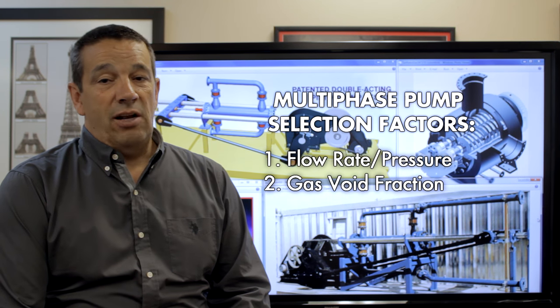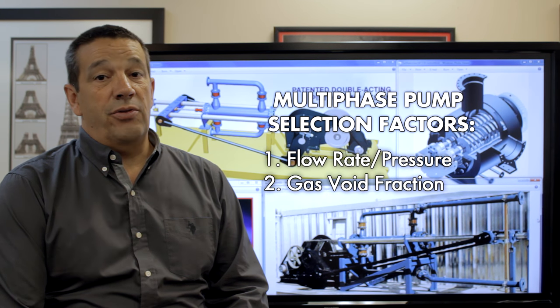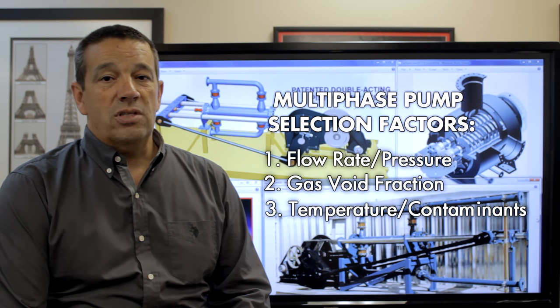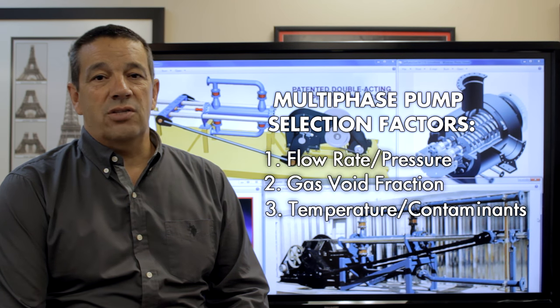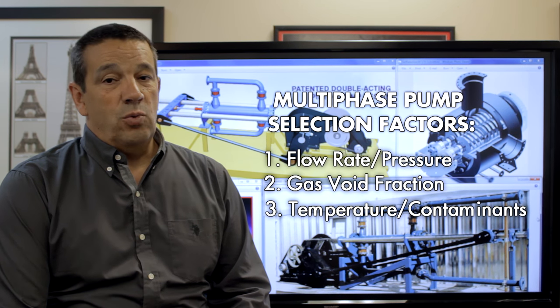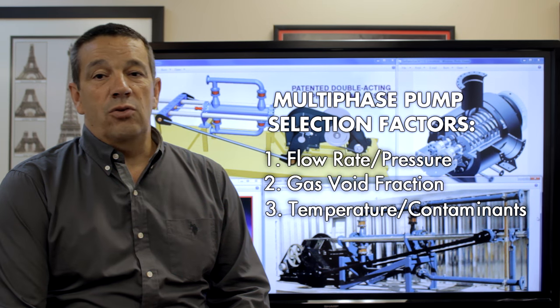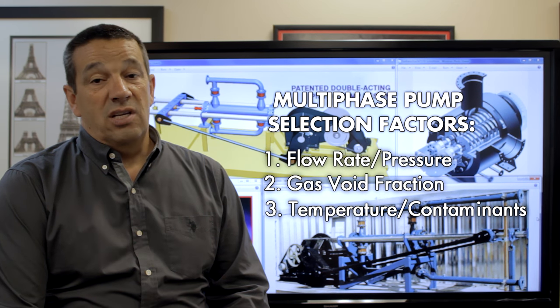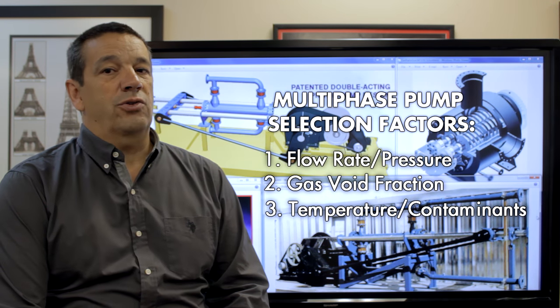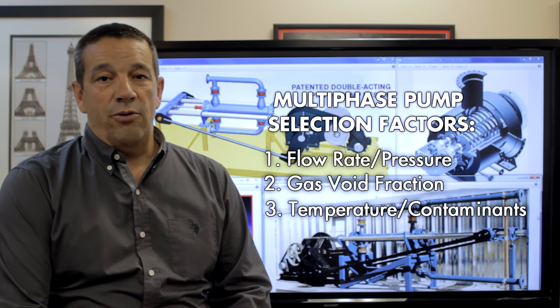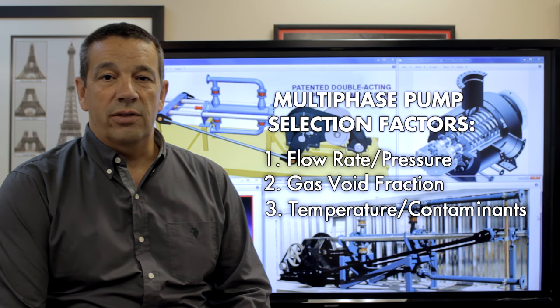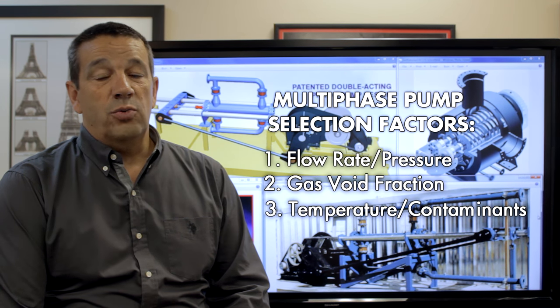Some pumps handle gas void fraction better than others. The other things to consider are temperature and contaminants. Temperature is important — when we're looking at SAGD projects we can get to temperatures which approach 200 degrees C, which limits what we can use, what metallurgy we can use, and what elastomers we can use. As far as contaminants, those can include solids — some products are better suited for solids than others — as well as high H2S contents, high CO2 contents, and other products which are corrosive.